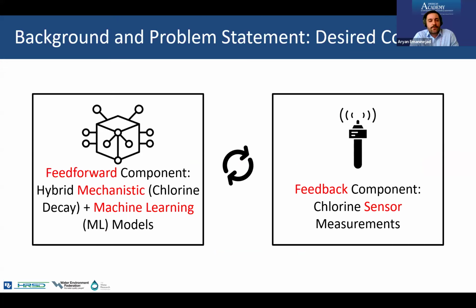The feedback component is based on a chlorine sensor that measures the amount of chlorine leaving the plant, and they estimate how much sodium hypochlorite to use. It has a lot of problems because it's a feedback control system - it's delayed, and they can't really have full control over how much chlorine they're using. But the feed-forward component we are offering is based on a hybrid approach using a mechanistic model based on chlorine decay and a machine learning model to offer that feed-forward insight, so we know our requirements in the future instead of relying on a feedback sensor.